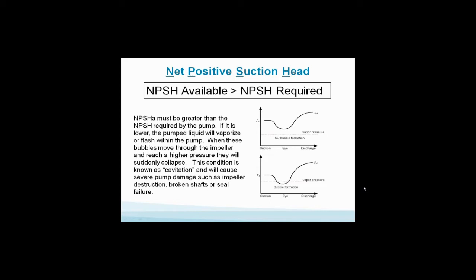We've got to measure the pressure. That piece of this is the gauge pressure, the suction flange gauge pressure. And the pump flows from the gauge pressure to the eye of the impeller, and because we're changing flow rates and we're putting work to it, the pressure actually drops before it hits the eye of the impeller and starts going back up. And that pressure drop of a pump is the defined required NPSH of a pump. And that pressure drop, if it falls below the existing vapor pressure, will cavitate a pump.